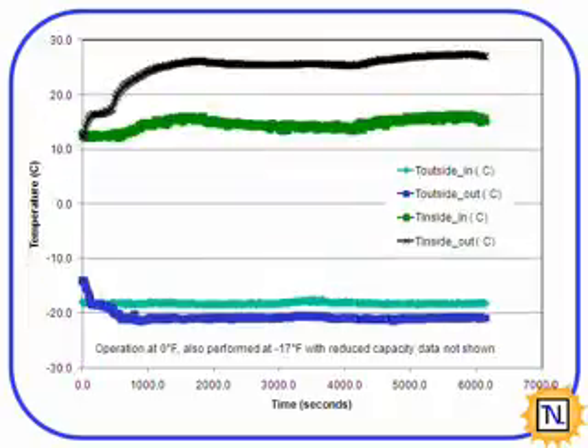And these are the temperatures. Even though it's cold, we're still getting some heat from the outside air, and it's coming in at 25, 27 degrees Celsius. So this is at 0 degrees Fahrenheit. We also ran it on that minus 17 degree day we had last week or so. The data is not shown for that, but it ran well. There was no damage to the system. It's important that if liquid refrigerant gets back to the compressor, it can damage components, so we want to see that it's been built properly so that we're not having any of those problems so far.